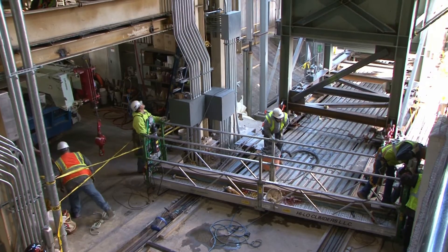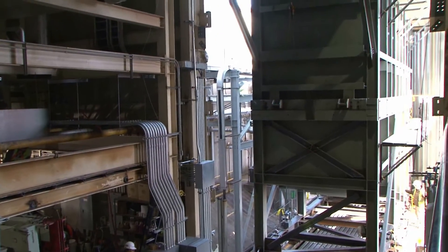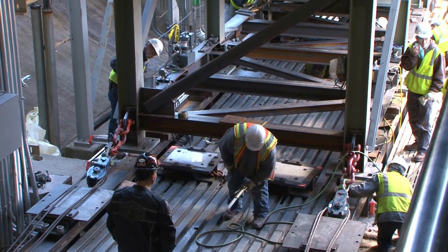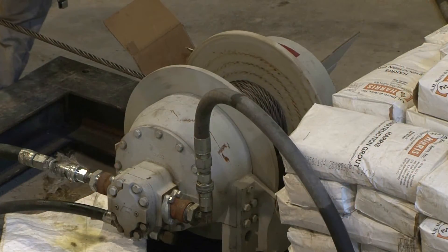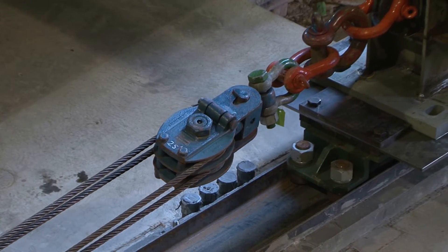The pull process involves the unit being erected on steel blocks on top of this rail assembly. What we have to do then is jack up the unit, remove the steel blocks, and put in the rollers that it's going to slide on. We're doing this jacking in one-eighth of an inch increments at a time at eight different locations, so the unit stays level without stress. Once it's on the roller, it's somewhat anticlimactic — it's hooked up to the winches, pre-reeved with cables and snatch blocks, and it rolls in.